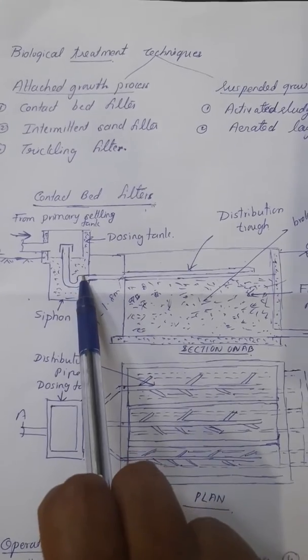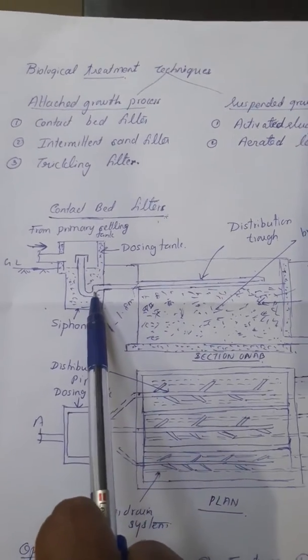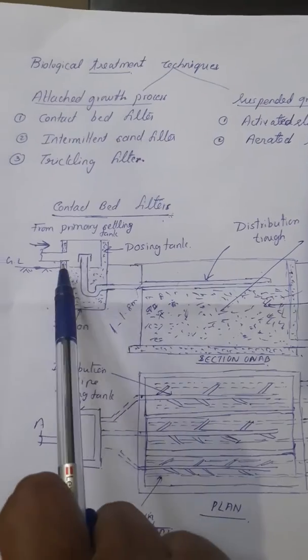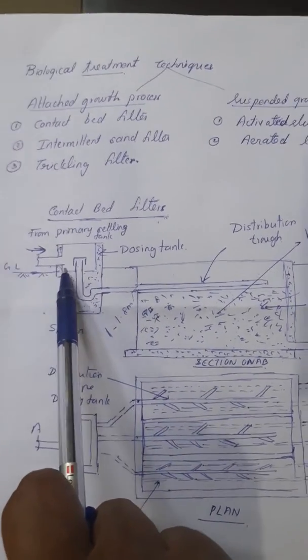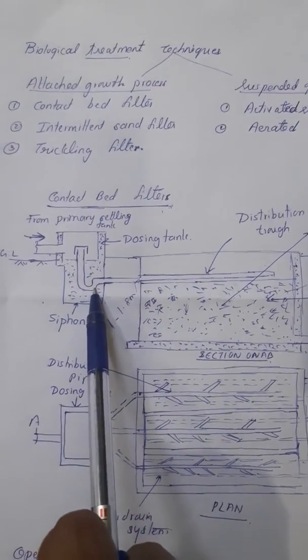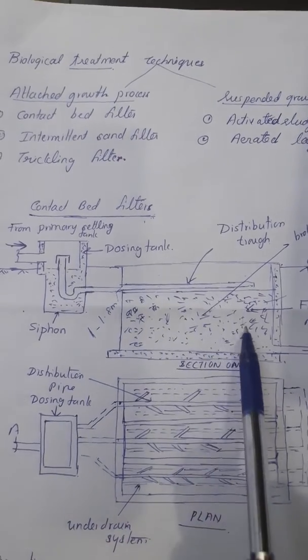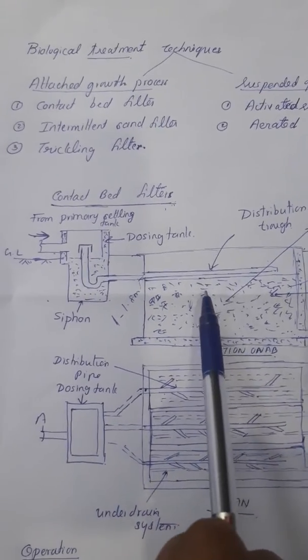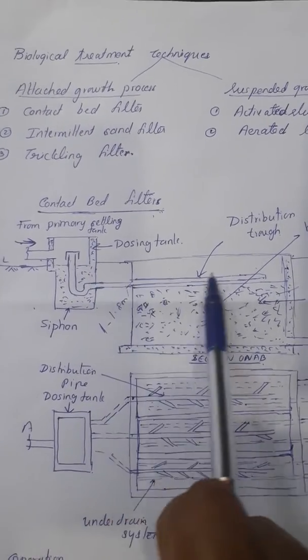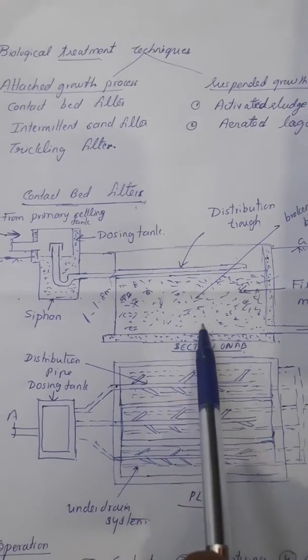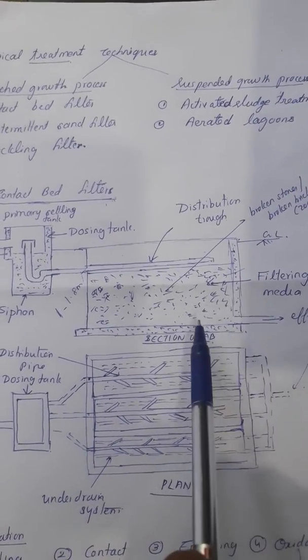A siphoning dosing tank is provided to serve 2 or 3 contact beds. The effluent from the primary settling tank is first received by this dosing tank and then distributed over one contact bed at a time. The effluent after passing over this coarse filter media is collected at the bottom and conveyed to the under drain system.